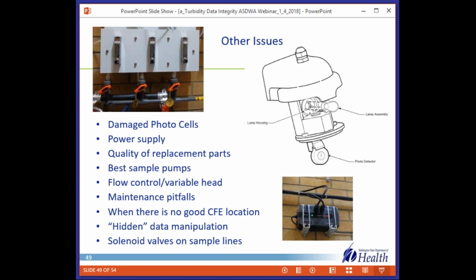A third one I labeled maintenance pitfalls. We've seen this at a number of plants where the flow gets interrupted to the turbidimeter, maybe during maintenance, and not restored when the system goes back online, or the instrument is placed into hold mode for calibration, and then they forget to take it out, so it remains in hold mode. And sometimes this can happen for, you know, a weekend. It always seems like it happens on the Friday. So maintenance pitfalls and SOPs and operator training, those are the solutions to that one.